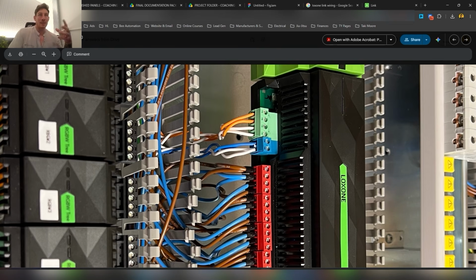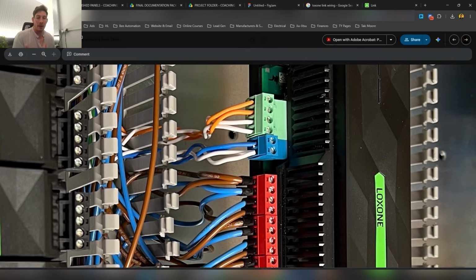You'll be racking your brains trying to find out where this issue is. You're doing a link diagnostic in the software and you're like, where the hell is this coming from? So it pays to take your time to make sure you're stripping it back the right amount. You don't want to strip it back too much where there's exposed copper cables here, because then it's unlikely, but something could short across there, if someone's modifying the panel, or a bit of swarf or debris or something.